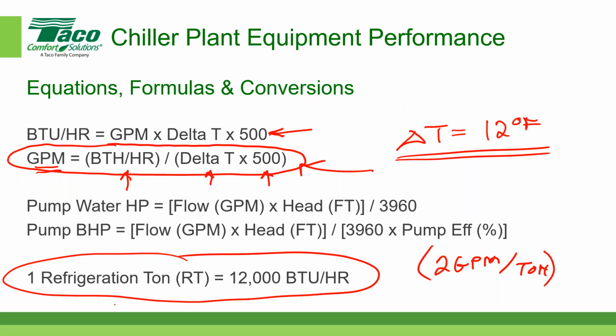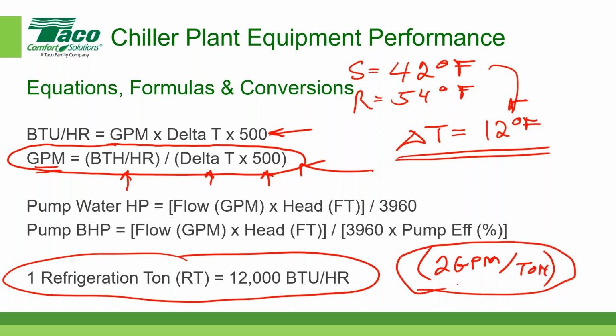So again, if you have a chiller plant and you're delivering water, let's just make up an example. Let's say you're delivering water at 42 degrees Fahrenheit, so we'll make that supply, and the return water is approximately 54 degrees Fahrenheit. That's a delta T of 12 degrees. And that means we're going to use 2 GPM per ton for a chilled water distribution.